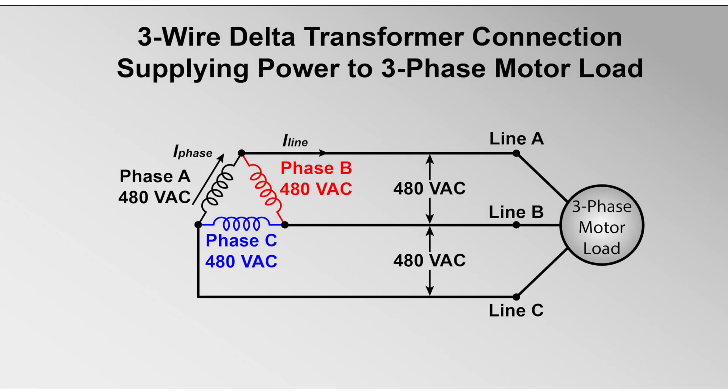Shown here is a typical three-phase, three-wire delta-connected transformer. The delta-connected transformer consists of three transformer windings connected end-to-end. For these transformers, phase voltage equals the line voltage and the line current is equal to phase current times 1.73.